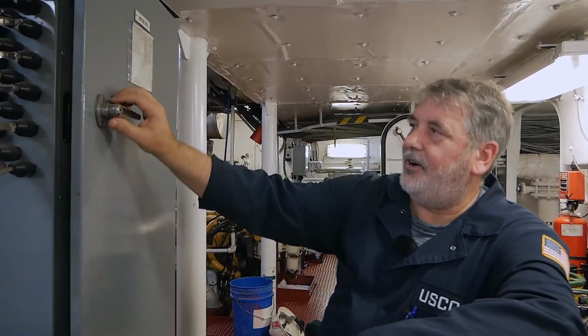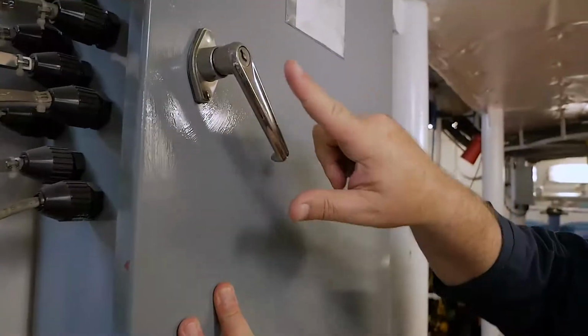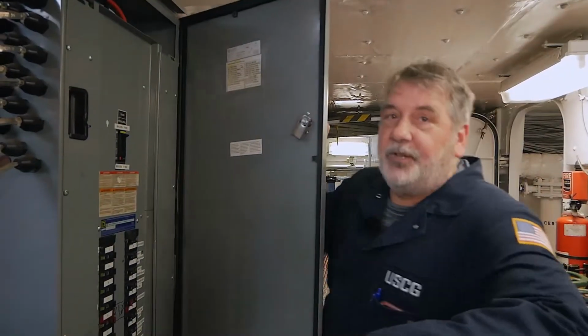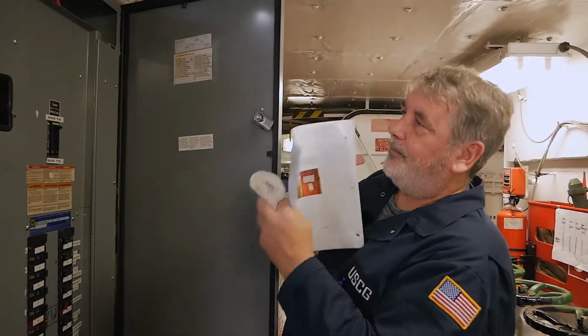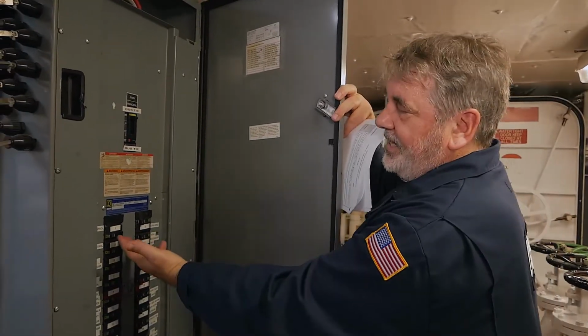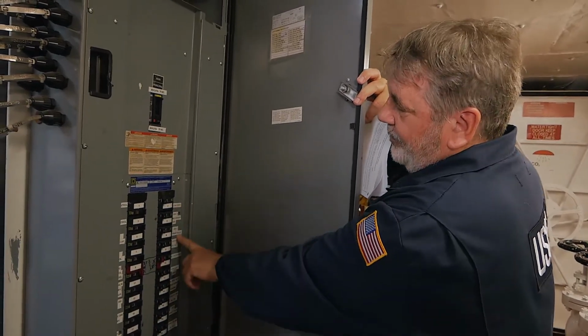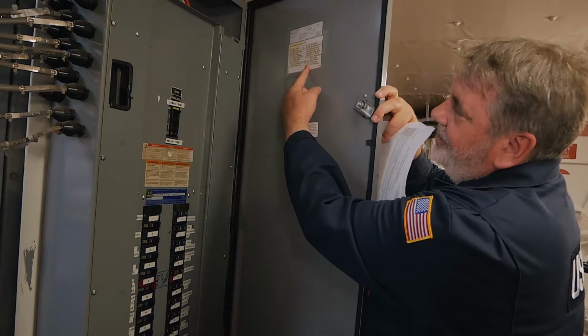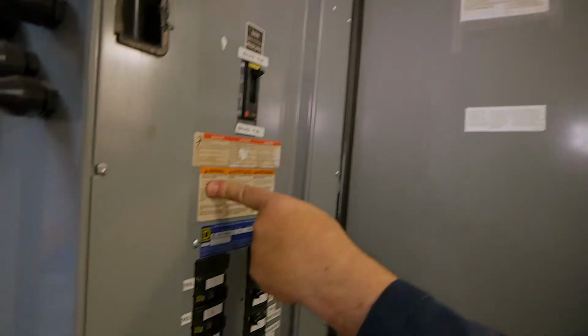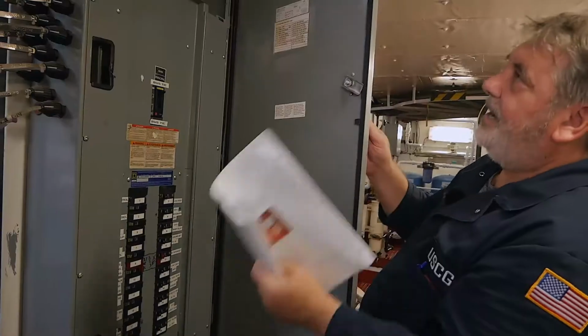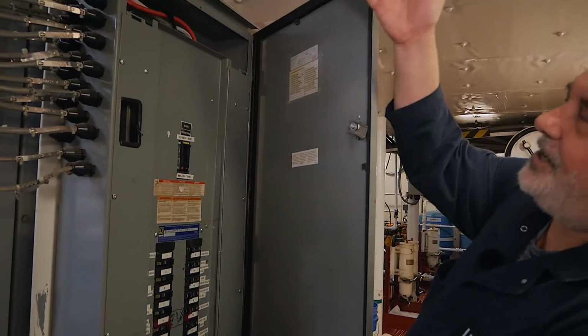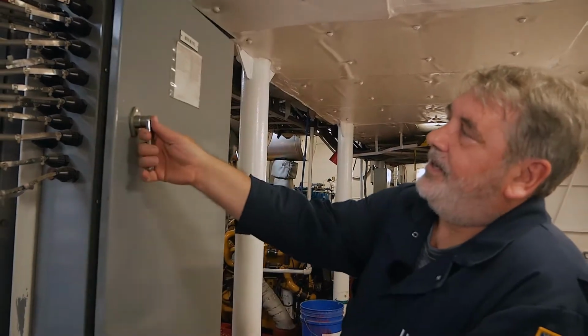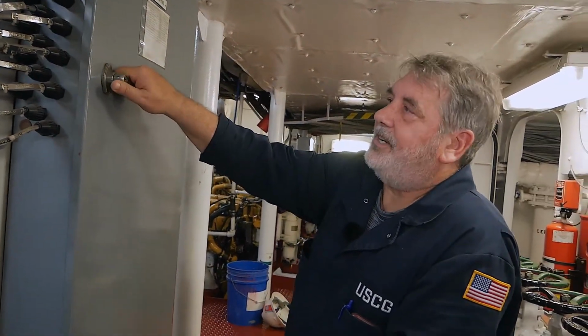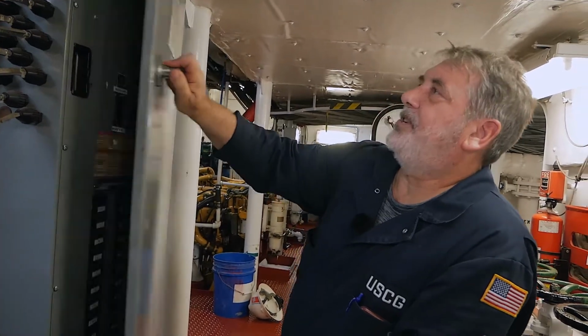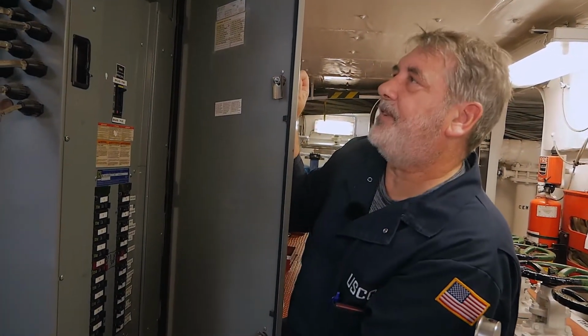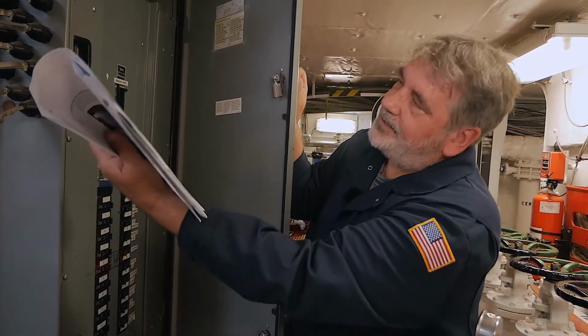The handles here are also lockable. As you can see, you can lock these with a key, and most breaker panels should be lockable. Inside, again, we have the breakers labeled with what they do, another directory as well. You can see the warning labels of high voltage, and again, this enclosure is drip proof. It is certified and rated for installation in an engine room. Most distribution panels meet NEMA 250 ratings. The cables make entry on the side.